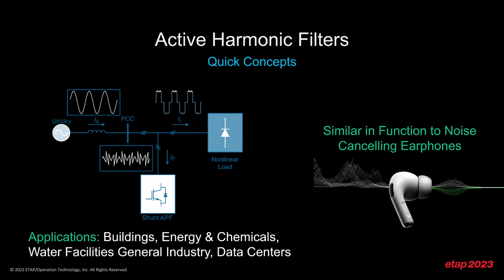They can vary from several tens of amps to several thousands of amps, enabling an optimal solution for each type of application. And the ability to scale from several tens of amps to several thousands of amps is not by one individual harmonic filter, but by combining different master and slave units. So of course, through this, you can use them in low voltage and medium voltage networks. And they're fundamentally power electronic devices that are installed typically in parallel, or in a shunt manner, to the polluting load. It monitors the line current as well as the customer requirements that are programmed. And then it generates for each harmonic frequency a compensation current that is in perfect phase opposition to the polluting current.